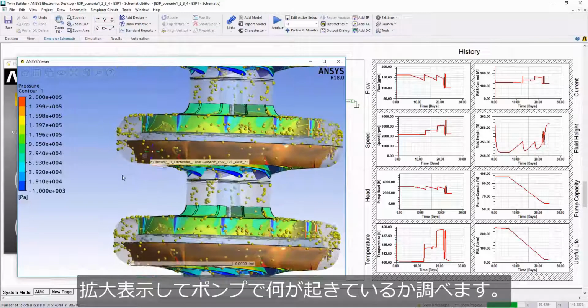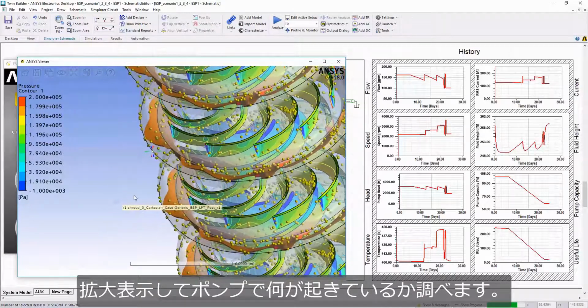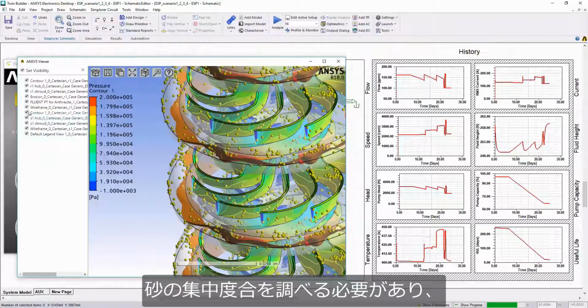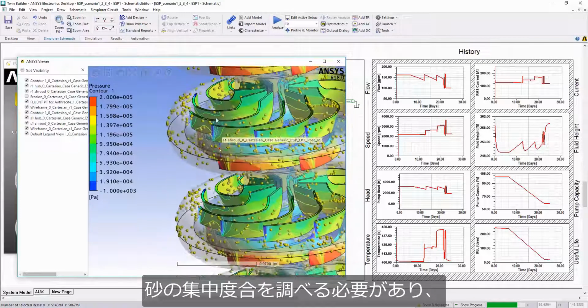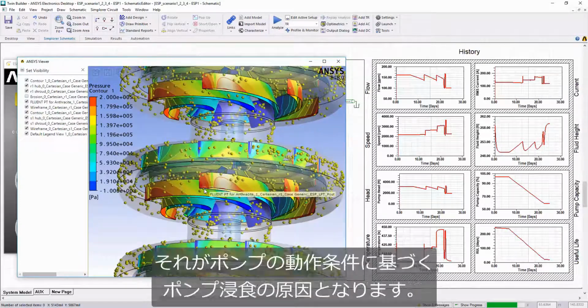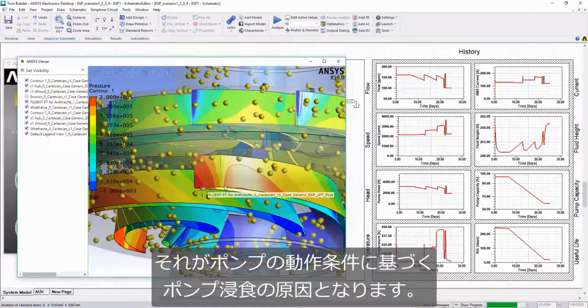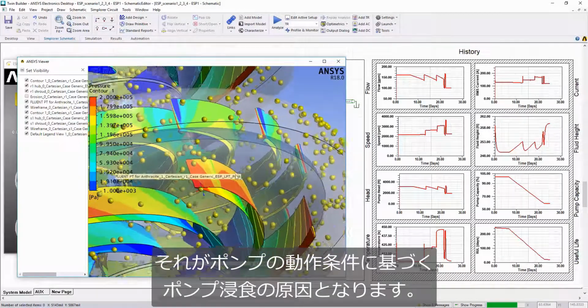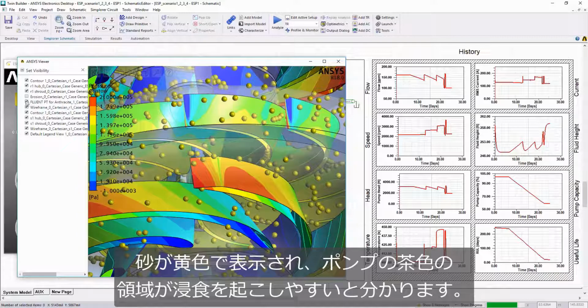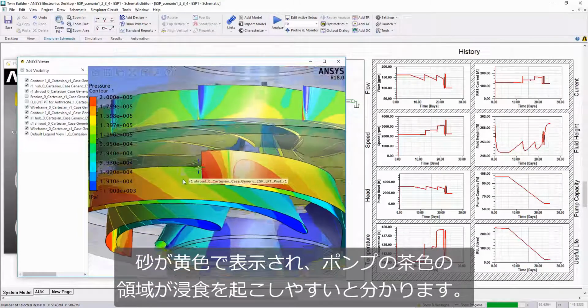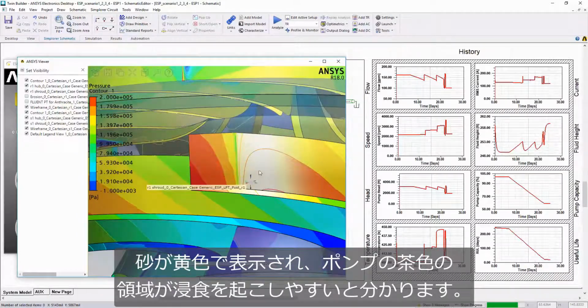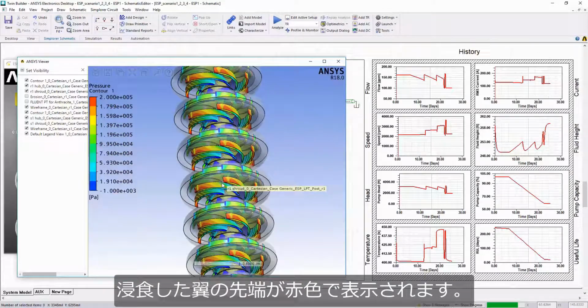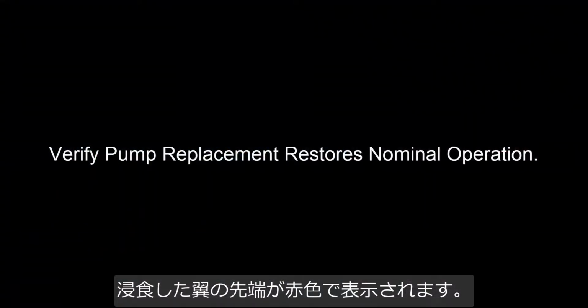We can zoom in and take a look at what is happening to the pump. We need to confirm that the amount of sand concentration is the cause of the pump erosion based on the operating conditions of the pump. We can see the sand in yellow and the brown areas of the pump that are prone to erosion. The eroded tips of the blades appear as the red areas.